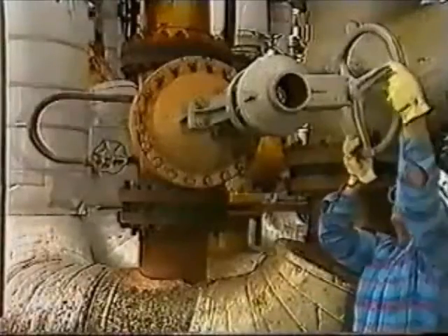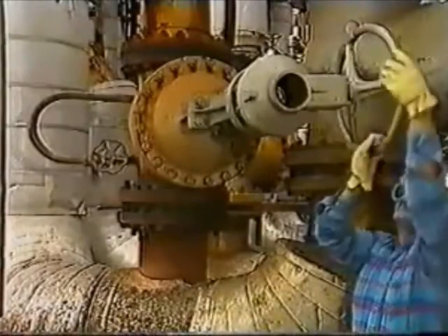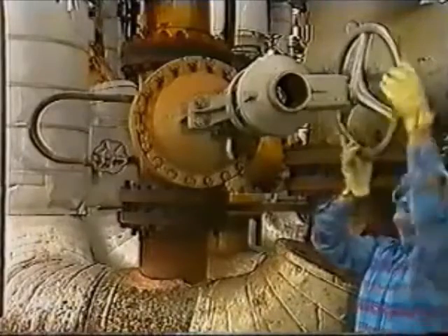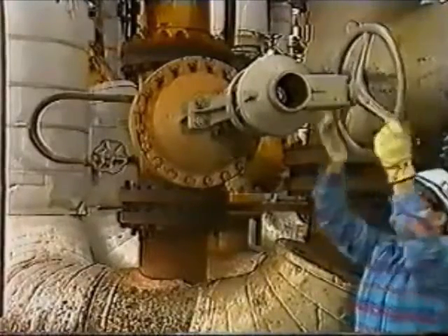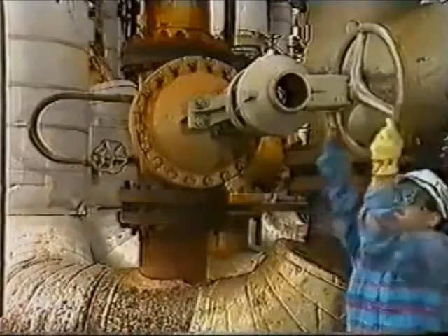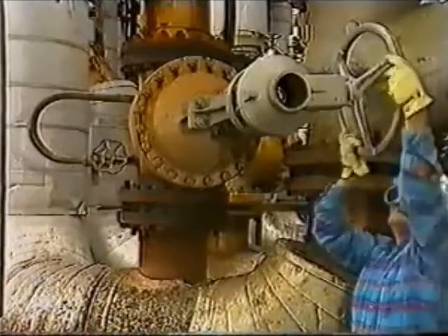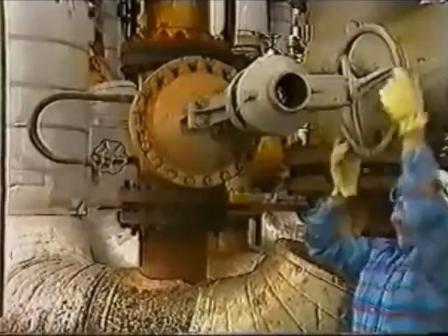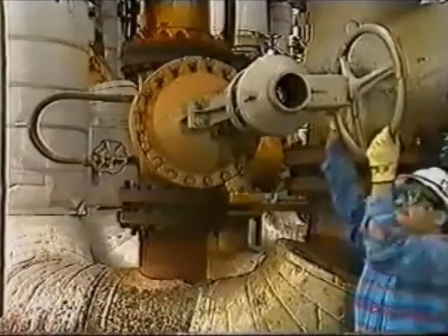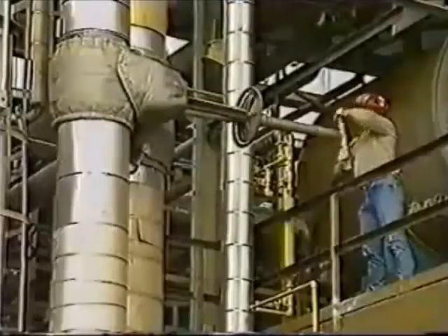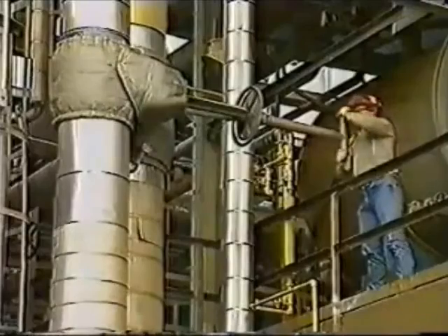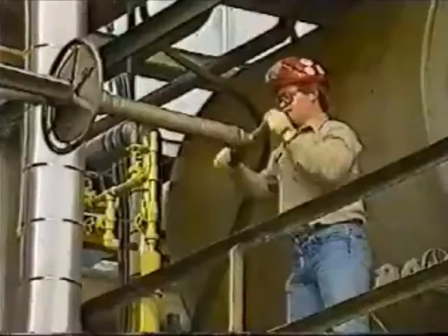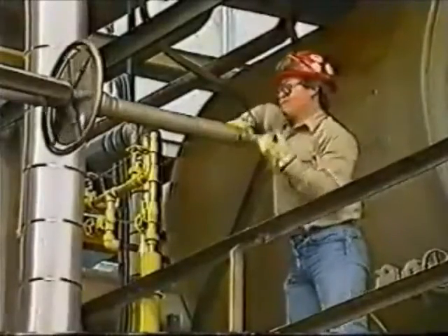A large valve requiring a lot of power to operate does not necessarily require a powerful motor to do the job. If a system of gears is attached, the power needed to operate the valve is reduced, and the valve can be positioned manually. Sometimes valves must be located in areas that are hard to reach. When this is the case, an extension stem or a sprocket wheel and chain can make the valve easier to operate.